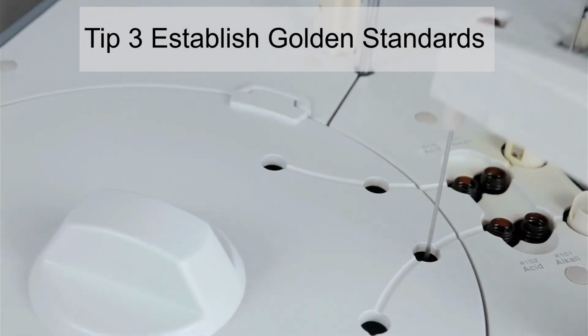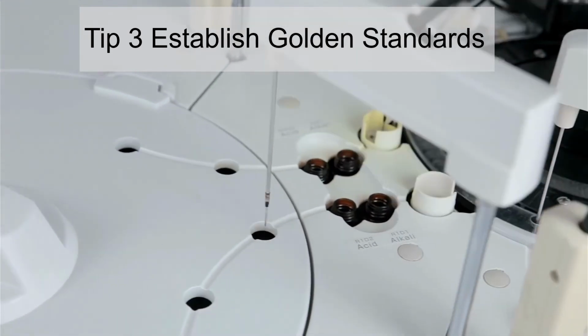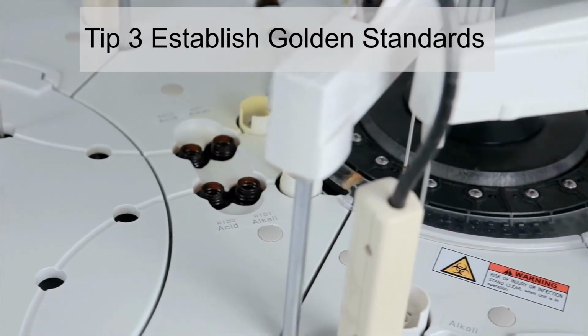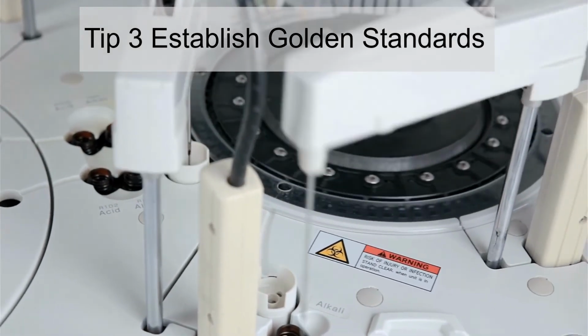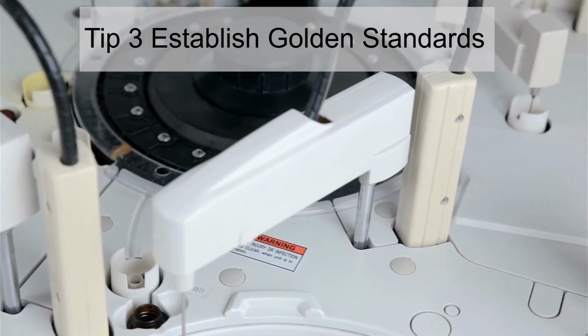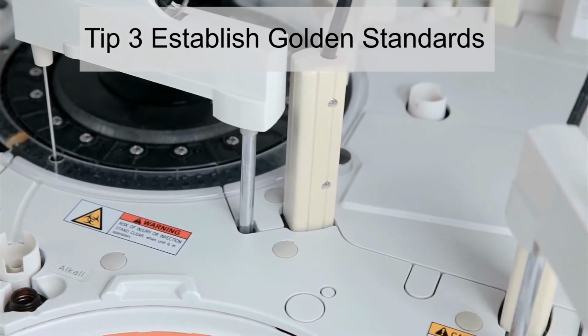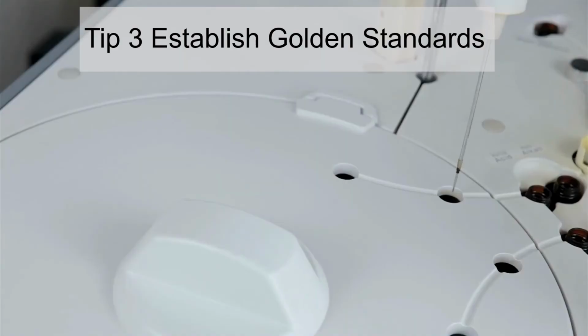Tip number 3 would be to establish the golden standards. Golden standards is used to verify the measuring equipment's ability to measure accurately. A measuring equipment should be verified with a known measurement golden standards at a regular interval. An accurate golden standard must be established to cover the range of the measurement, and it should be properly maintained.